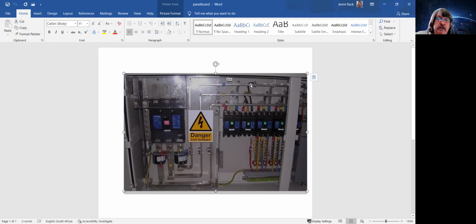And so if you suddenly used very small cables, let's say, for instance, there was a 250 amp and then a 100 amp feed out of here, and you used a 100 amp cable here, you might find that the cable itself cannot withstand 10 kA or 20 kA of the main protection here, and so would be at risk. Mechanically and electrically, it could be a problem going forward.